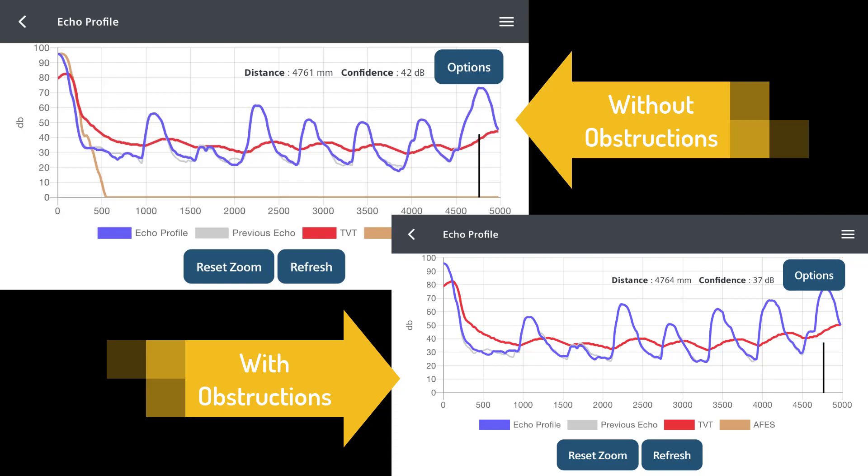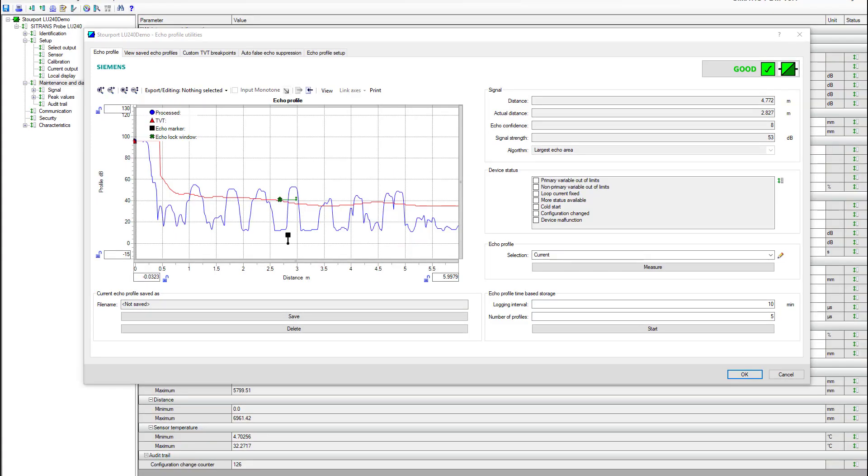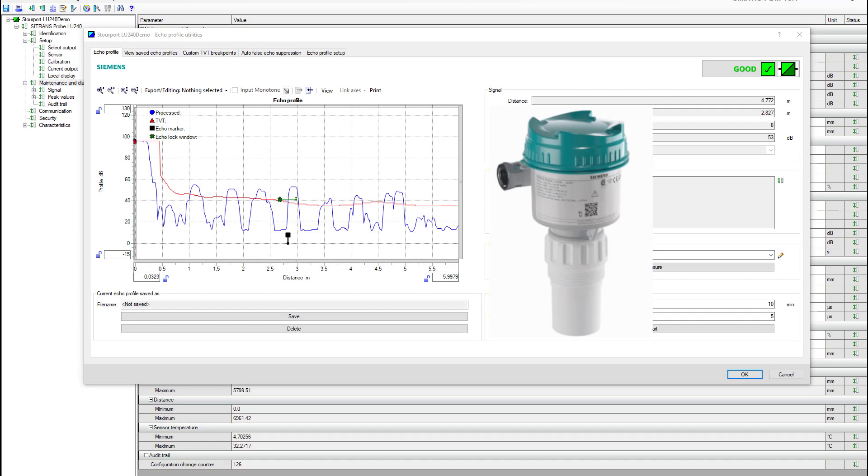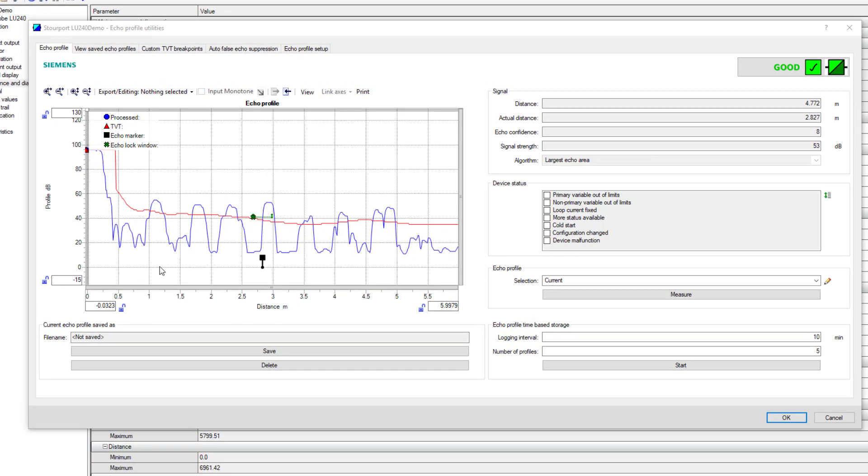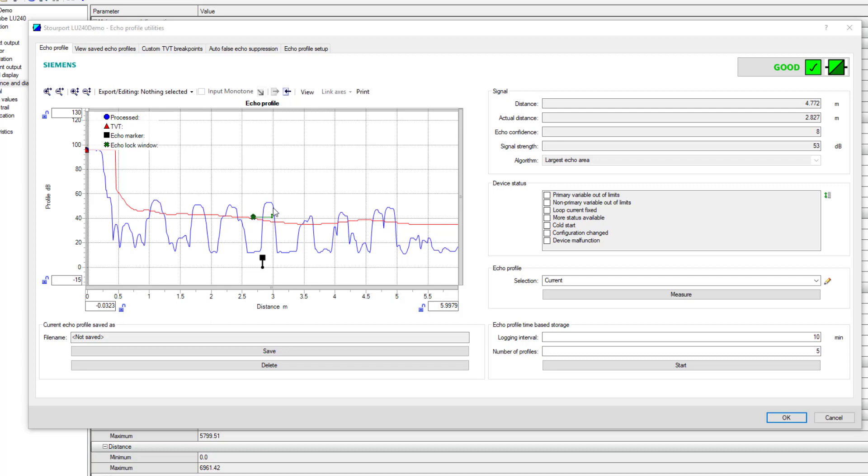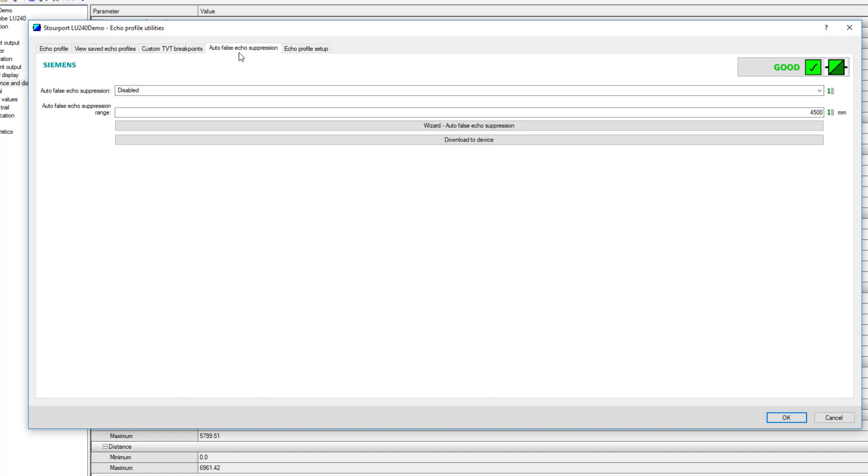We're back looking at the LU240 ultrasonic device now with all the obstacles in the way. We've got a slight increase on some of these. The one actually up closer is the one that's causing us the biggest problem. Because that is there, it's attenuating the signal. The far end signal is getting attenuated the most, but it's not the end of the day for this device. We're going to have a look at something called auto false echo suppression.